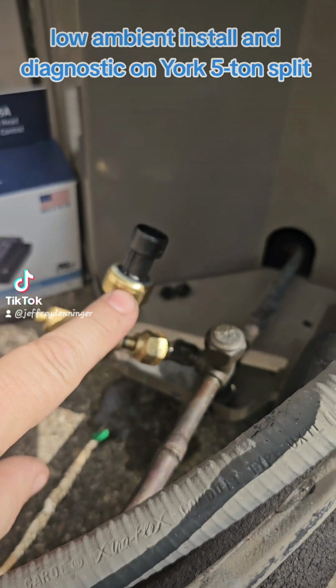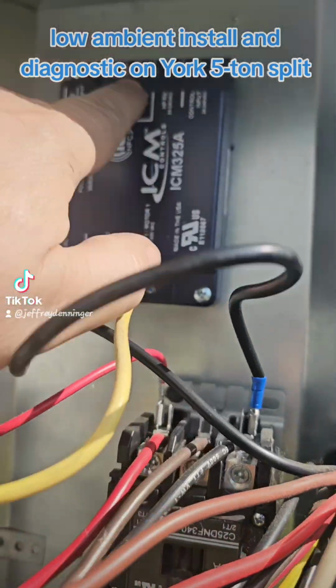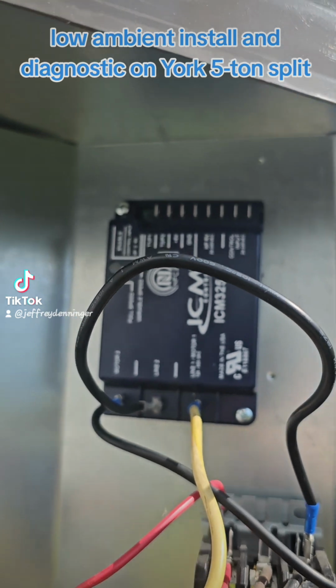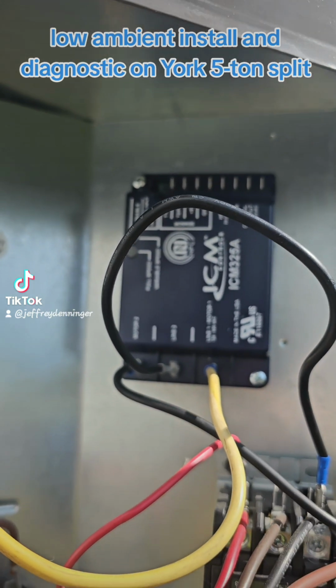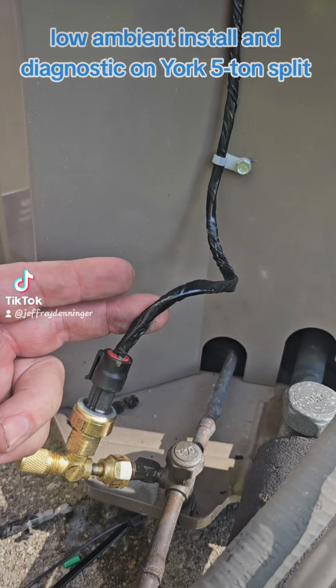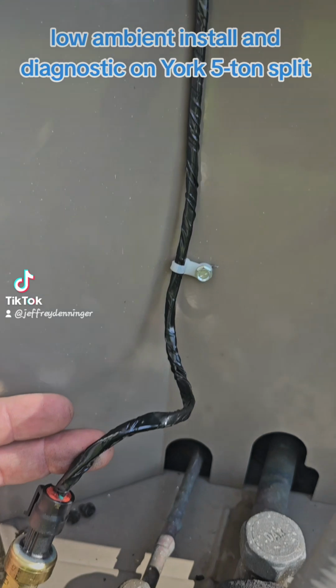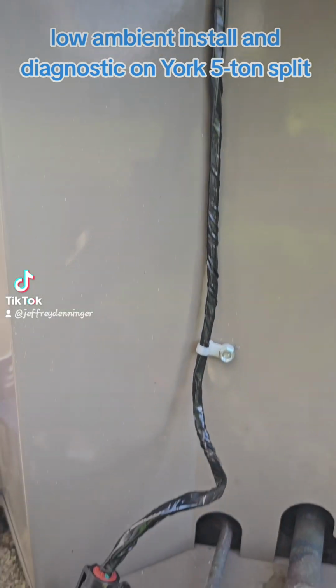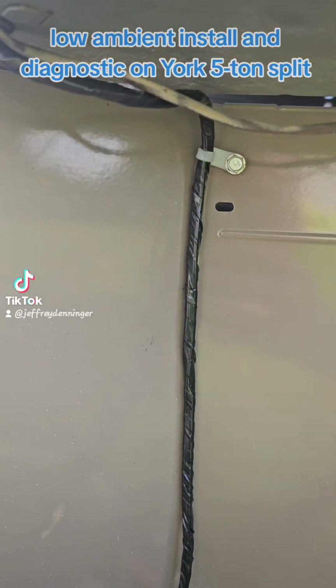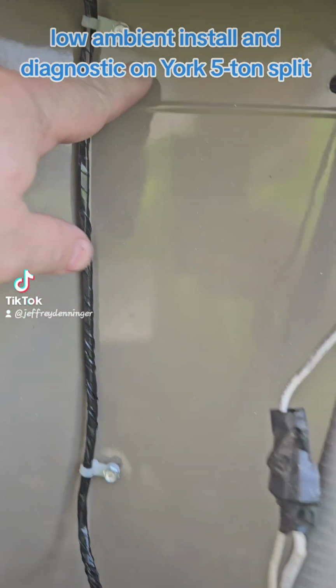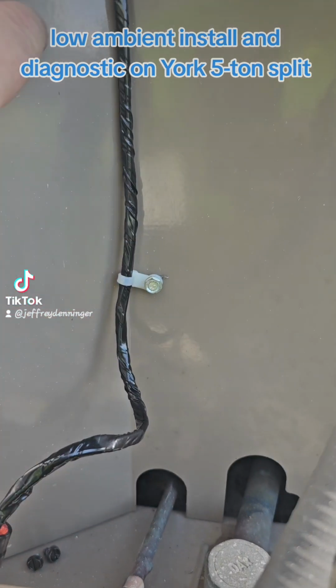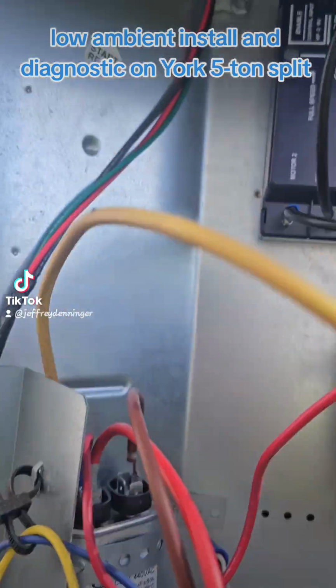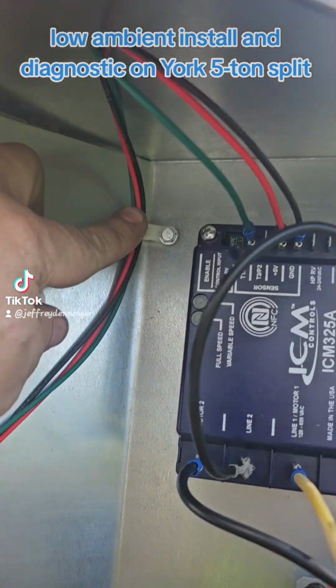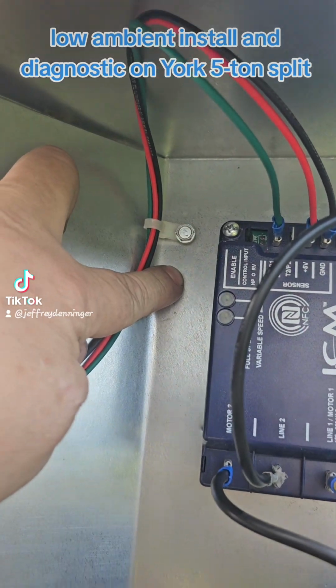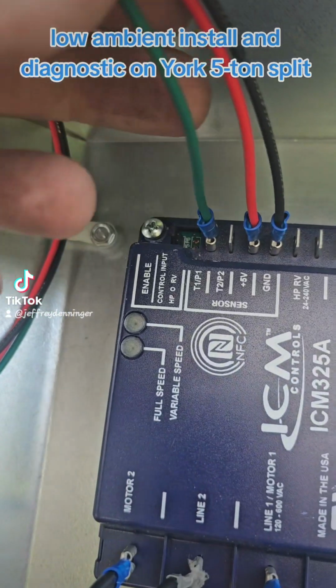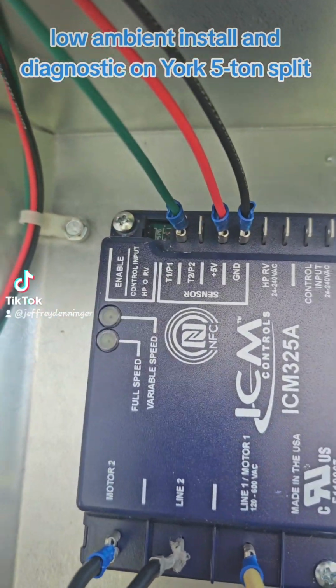Next, we're going to wire in the pressure transducer up into here. I'll include the wire diagram for that one too. Okay, I went ahead and I wrapped the wires for the pressure transducers because I don't have loom on me. But then I took it and I secured it. I made sure where I was drilling that there is no part of the coil so I can't hit it, no leaks. Came all the way up inside again. Made sure that there was no piping behind it. And I wired my pressure transducer in according to the manufacturer's instructions.